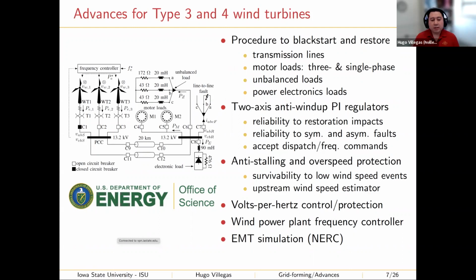There could be cases during the restoration process where wind speed reduces suddenly, and at those instances the wind turbine can stall. Why? Because the converter interfacing the grid could be transferring more power than the turbine can provide. In that instance, the wind turbine might start stalling. Then it was necessary to invent a new anti-stalling protection for reliable grid-forming operation. I call this survivability, because we are trying to survive these low wind speed events during the restoration process. The whole goal is not to de-energize the grid during the restoration.